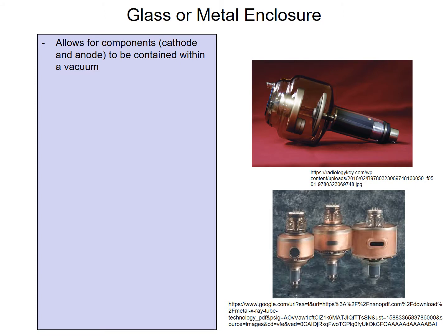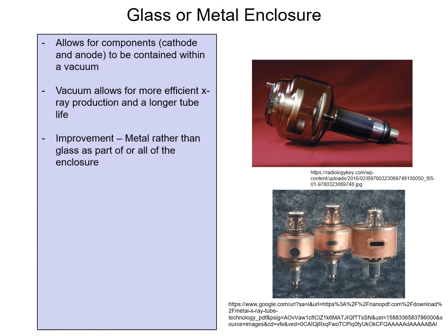When we talk about the X-ray tube, X-ray tubes today are either glass or they're metal, or they're a combination of both. Okay? It allows for the components, the cathode and the anode, to be contained within a vacuum. Remember, to produce X-rays efficiently and effectively, those electrons streaming over from the cathode to the anode, you don't want them to bump into any air molecules, so we need there to be a vacuum. As I just mentioned, the vacuum does allow for more efficient X-ray production and therefore a longer tube life. Metal is being used more often for, as I mentioned, either the whole tube itself or for a part of the tube.